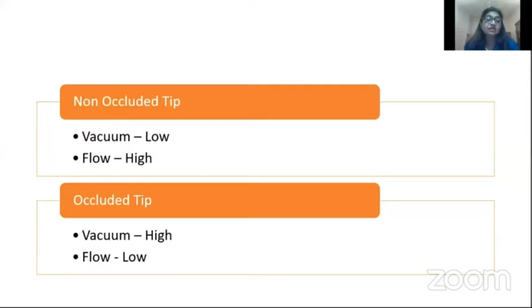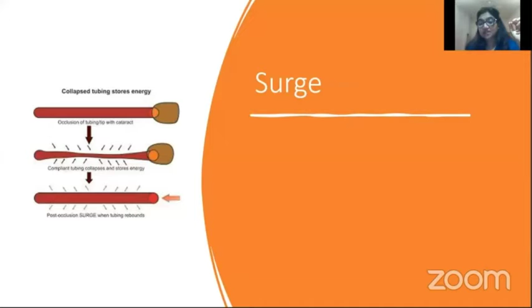If the tubings are compliant and not very rigid, there is a negative pressure which is created inside the tubing. Once the nuclear fragment is emulsified, this energy which is inside temporarily will pull the fluid from the anterior chamber, and the anterior chamber can collapse just for a fraction of a second. And this is what is called a surge. It is the situation when the outflow of the fluid from the eye exceeds the inflow, even if it is just for a fraction of a second.